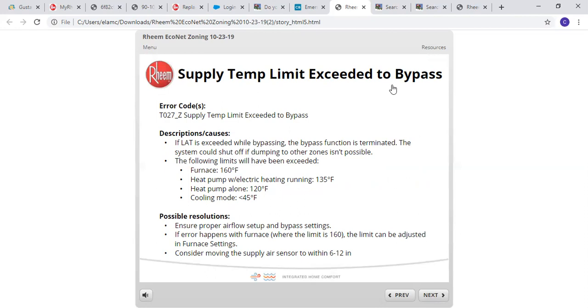Here's your supply temp exceeded to bypass. The T027Z supply temperature limit exceeded to bypass. Description or causes: if the leaving air temperature is exceeded while bypassing, the bypass function is terminated. The system could shut off if dumping into the other zones is not possible. So the following limits have been exceeded: the furnace, 160 degrees, heat pump with electric heat running, 135, heat pump alone, 120, or cooling mode, 45.